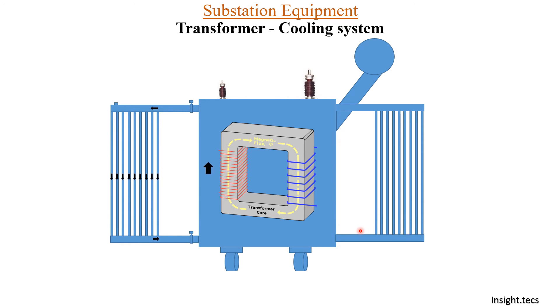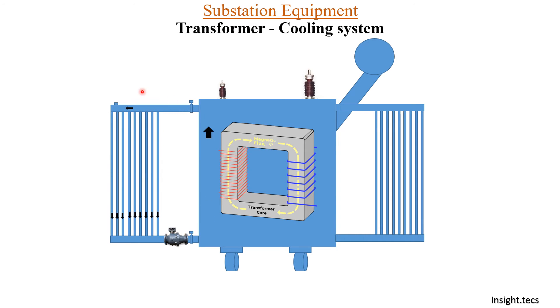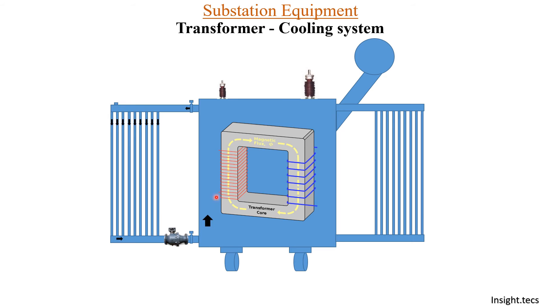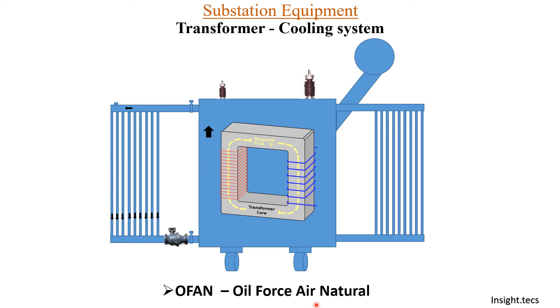One more system we can use is an oil pump. The function of the oil pump is to pump the oil more quickly inside the main tank, so the oil will circulate with more speed. As the circulation increases, cooling increases, and the transformer oil will remain at normal temperature, increasing the efficiency of the transformer. Since we are forcing the oil, this kind of cooling system is called oil force air natural, as the air is rotating naturally.